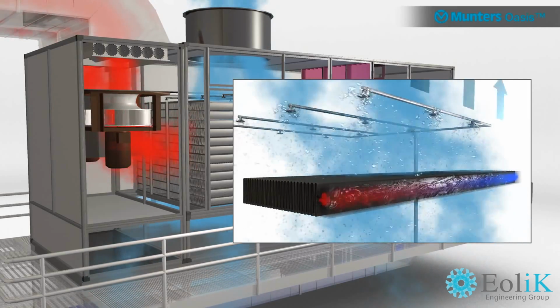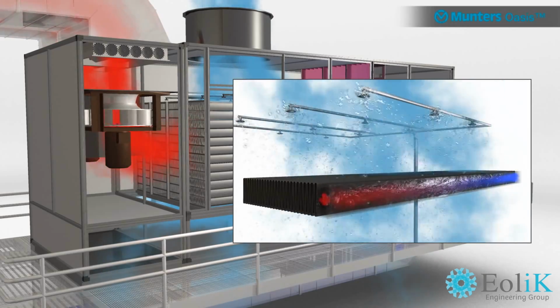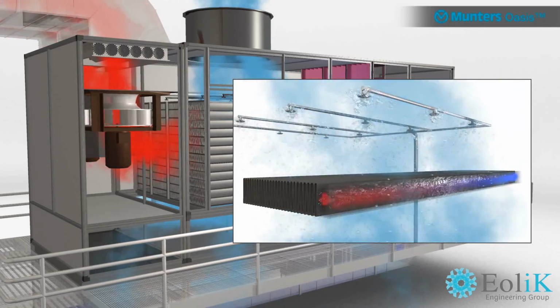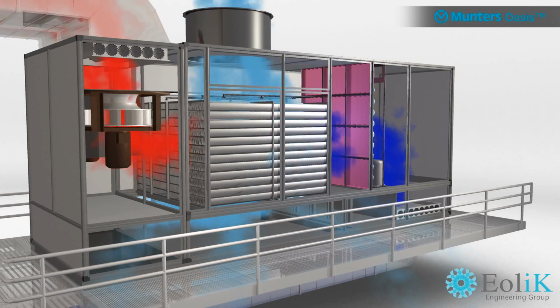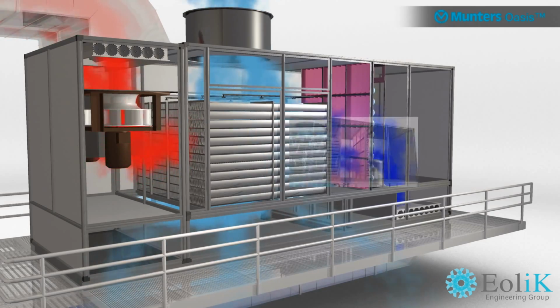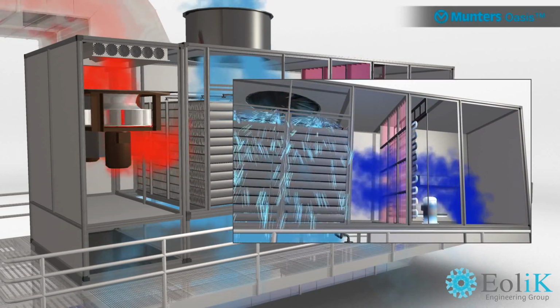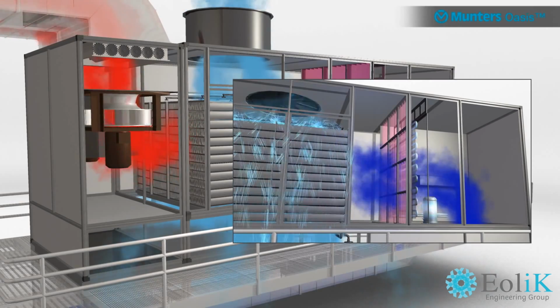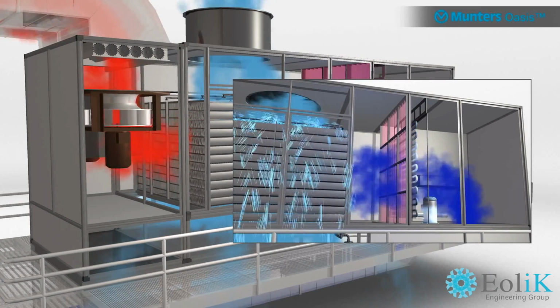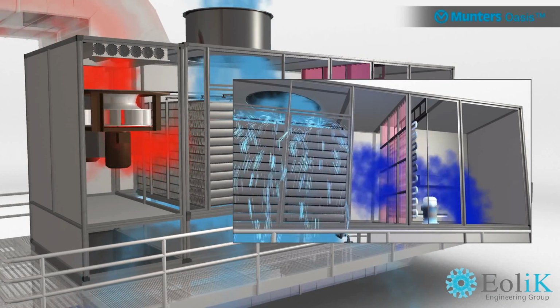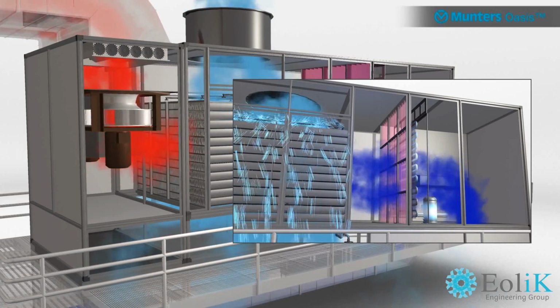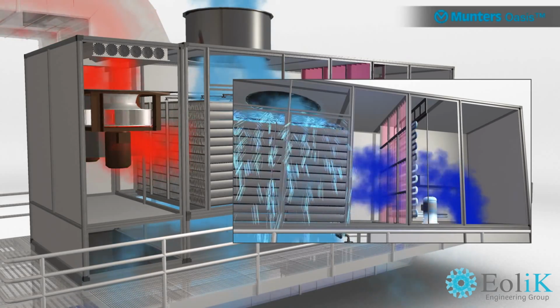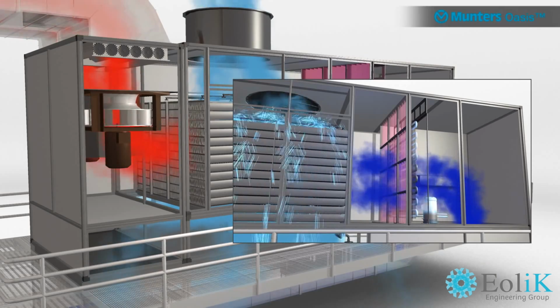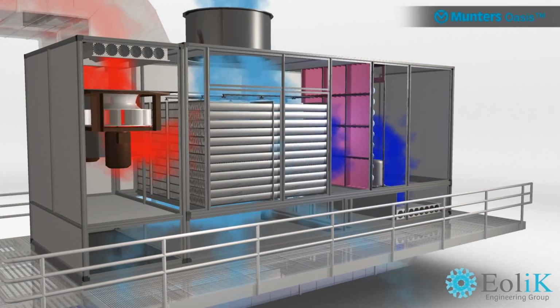Unlike other indirect evaporative cooling systems, Oasis can accept mains, potable, grey and harvested water without the need for reverse osmosis or other forms of distillation treatment. Oasis is also suitable for use in hard water areas. When the ambient air is too hot or humid, the Oasis system can operate in its third energy-saving mode, combining the indirect evaporative cooling process with the use of either direct expansion DX refrigeration cooling or a chilled water coil circuit from an independent chiller in order to satisfy Tier 4 requirements.